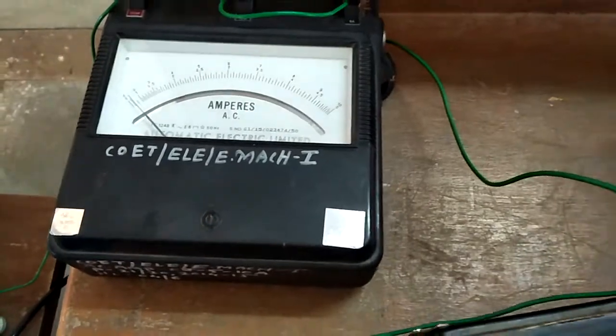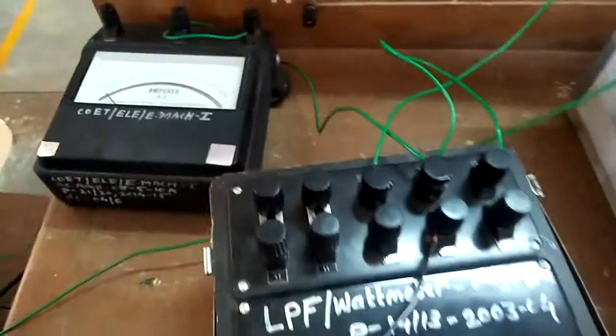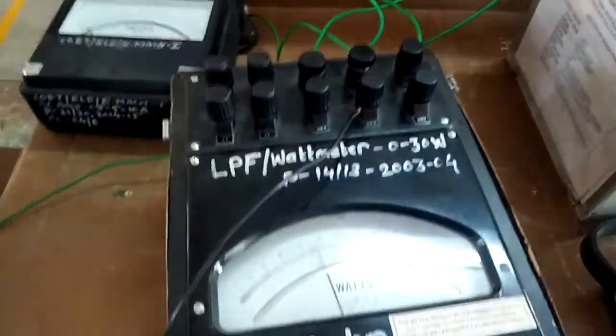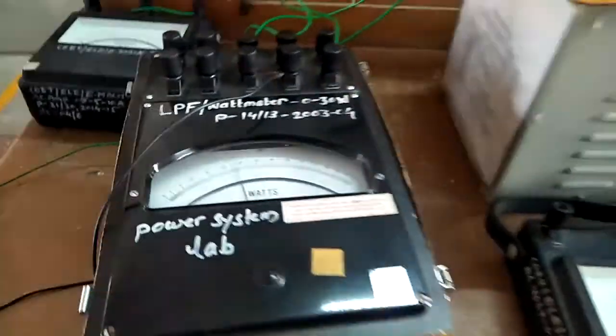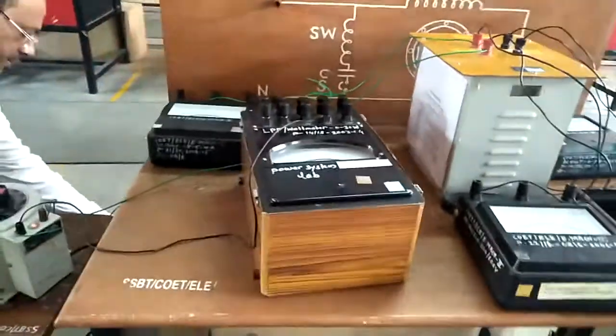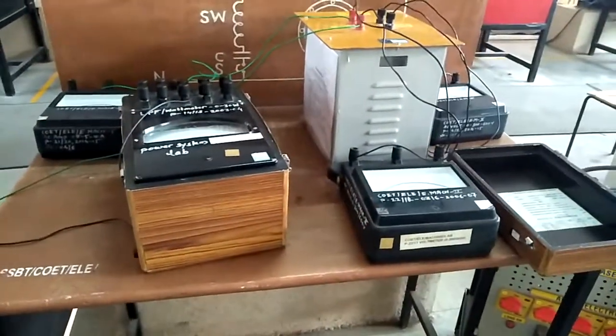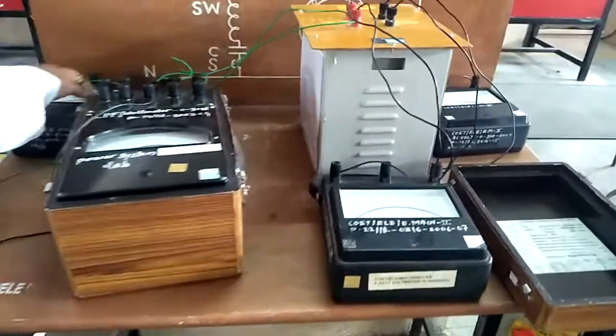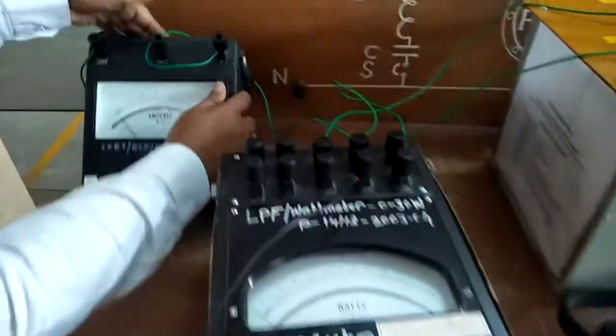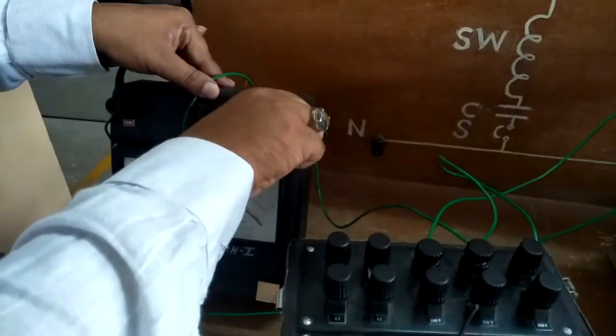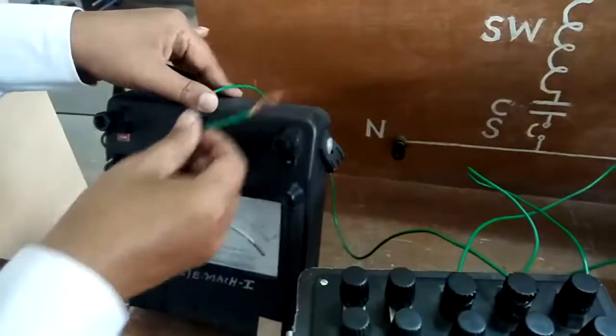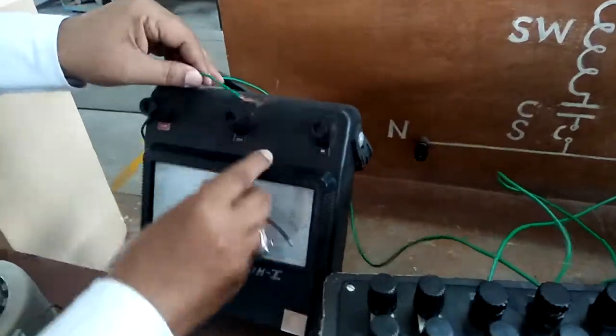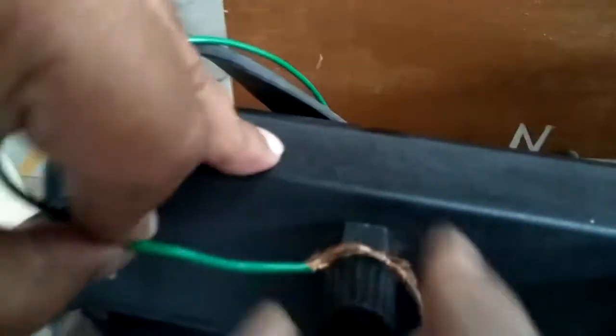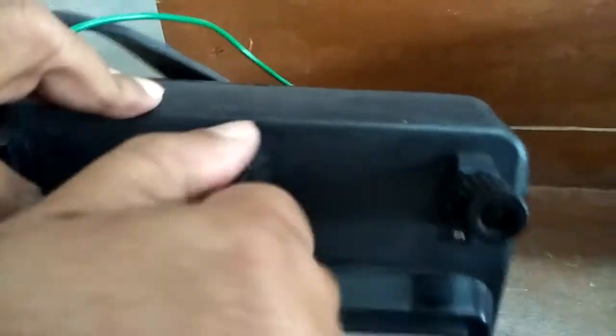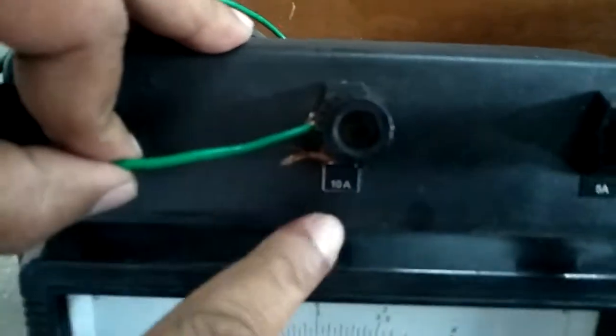Okay, so now after that what we will do is make the short circuit in the secondary winding. We will replace this wattmeter by our regular wattmeter because the current is very high. So the no load test is over. Now, because the rated current is 8.6, you are going to select the current range of 10 ampere. We have selected the current range of 10 ampere. See here, the current range is 10 ampere.